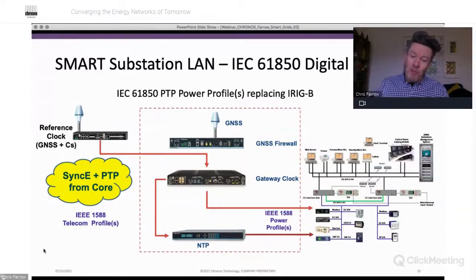We have reference clocks within our substation. We're showing, in the middle and bottom of the slide, two separate clocks, but one box could do both functions: delivering NTP, the network time protocol, for any workstation or client in the substation that needs time for timestamping events, and for very high precision applications needing microsecond or better accuracy, IEEE 1588, or PTP, the precision time protocol.